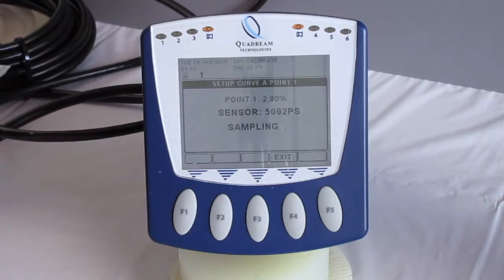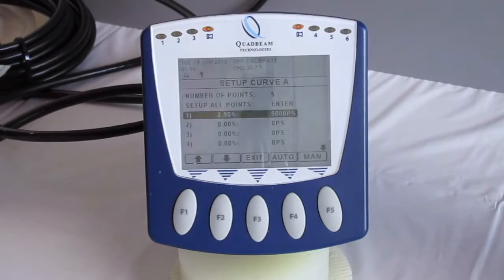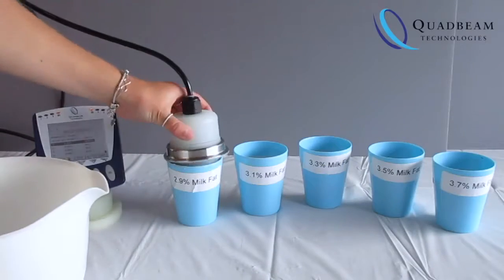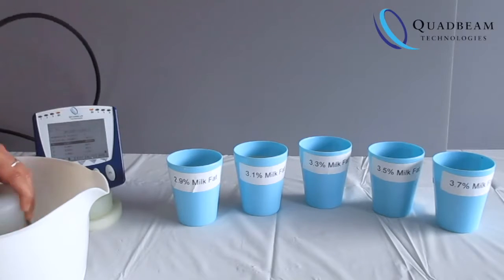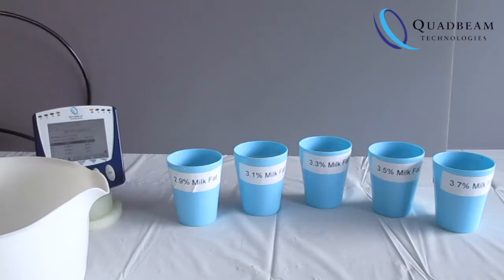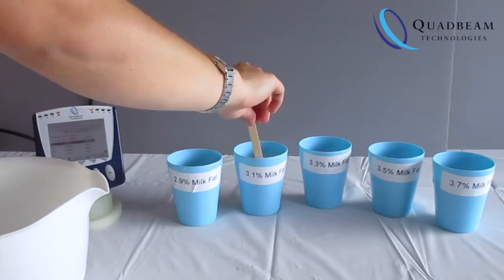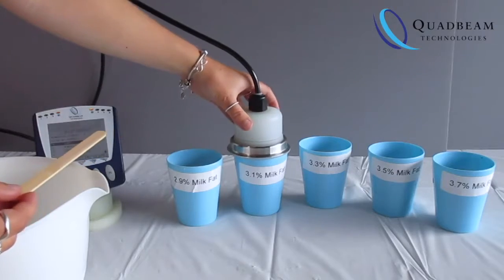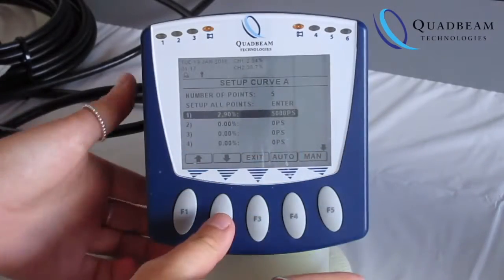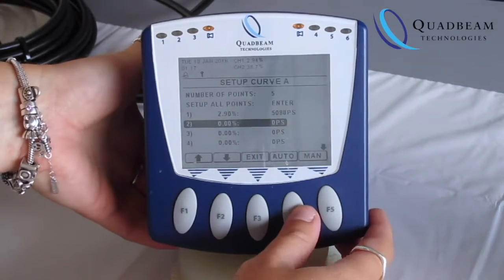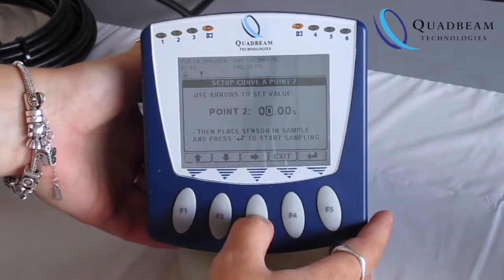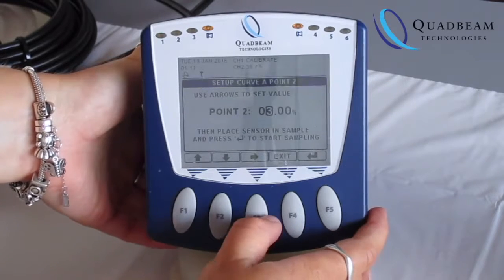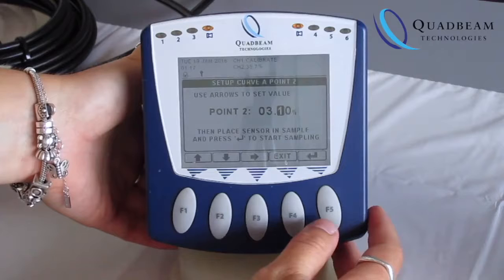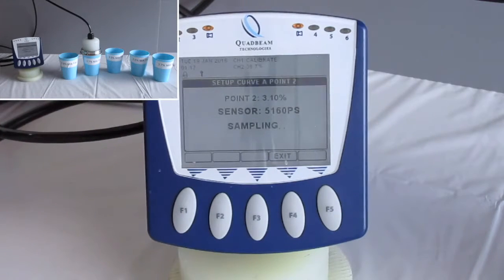Once the sampling is complete, remove the sensor, give it a good clean and dry. You don't want cross-contamination between the different samples. Ensure the sample's stirred, not overstirred. Bubbles will contaminate the reading. And then move through the same process again. Move to point 2. Input the value of the second sample. Then press enter. Again, it will apply that probe signal value to the value of the concentration that you've got in that sample.